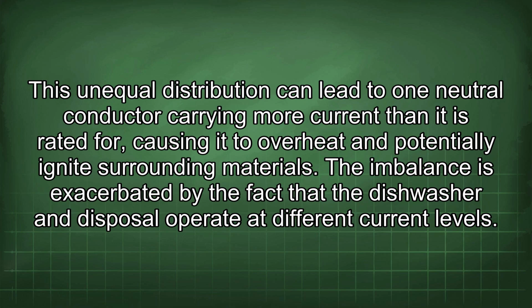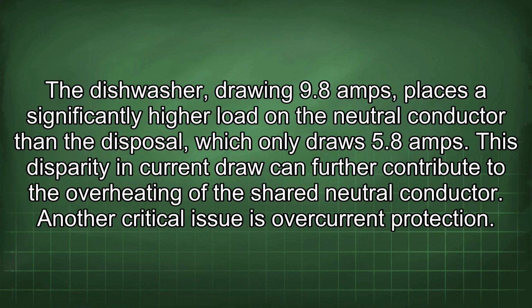The imbalance is exacerbated by the fact that the dishwasher and disposal operate at different current levels. The dishwasher, drawing 9.8 amps, places a significantly higher load on the neutral conductor than the disposal, which only draws 5.8 amps. This disparity in current draw can further contribute to the overheating of the shared neutral conductor.